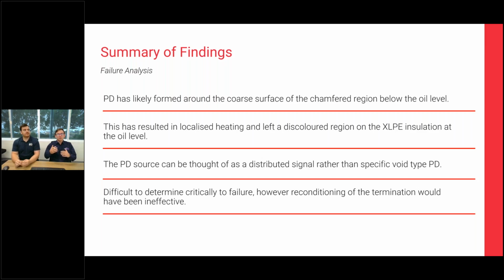So it was excellent for us to find that different style of partial discharge, and something to be aware of when monitoring oil-filled assets, especially with XLPE insulation. It was difficult to determine the criticality of this failure.